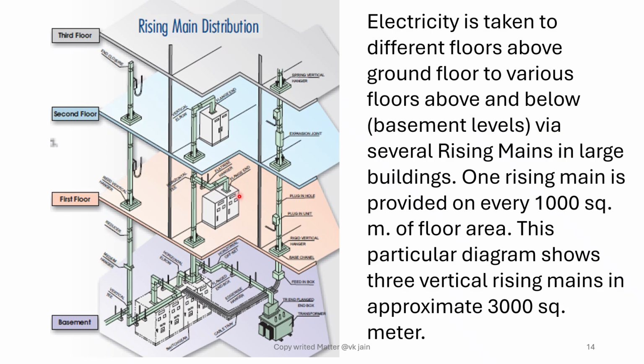The left hand side of this slide shows the rising main distribution system, which is vertical distribution from the main panel. There are three rising mains here. Electricity is taken to different floors above ground floor, to various floors above and below, via several rising mains in large buildings. One rising main is provided for approximately every 1,000 square meter of floor area. This particular diagram shows three vertical rising mains in approximately 3,000 square meter area.